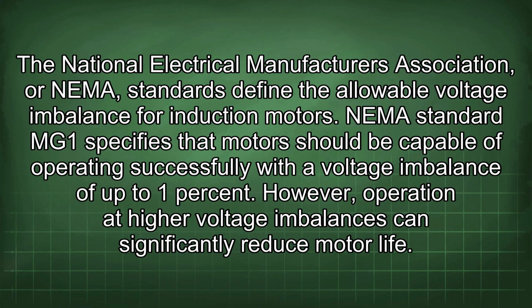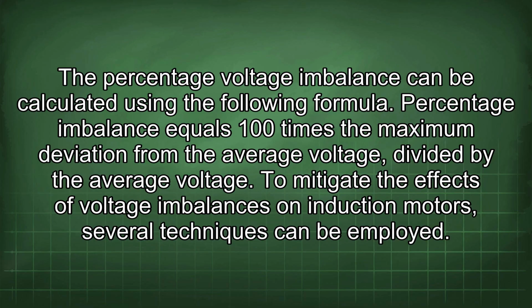NEMA standard MG1 specifies that motors should be capable of operating successfully with a voltage imbalance of up to 1%. However, operation at higher voltage imbalances can significantly reduce motor life. The percentage voltage imbalance can be calculated using the following formula. Percentage imbalance equals 100 times the maximum deviation from the average voltage divided by the average voltage.